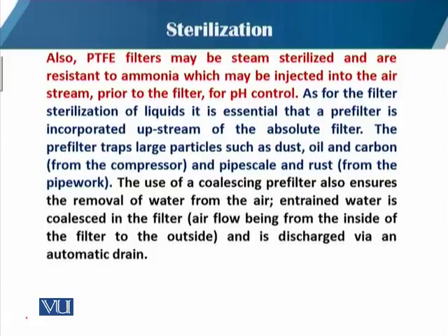Also, PTFE filters may be steam sterilized, because if we have to use those filters, we first have to steam sterilize them to ensure that the filter is free from contamination. They are also resistant to ammonia, which may be injected into the air stream prior to the filter for pH control. Sometimes we have to control the pH.